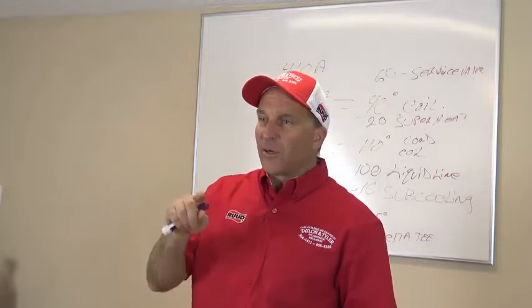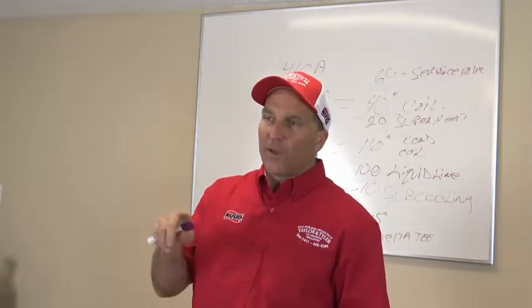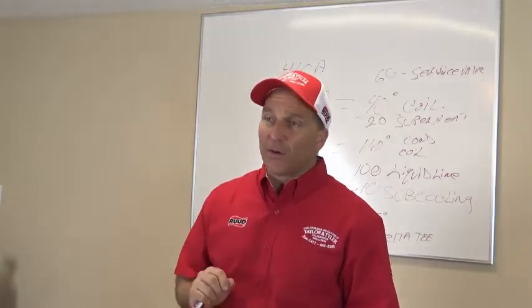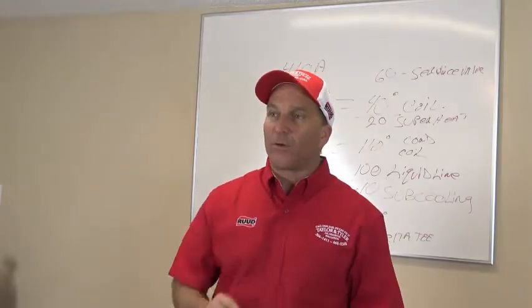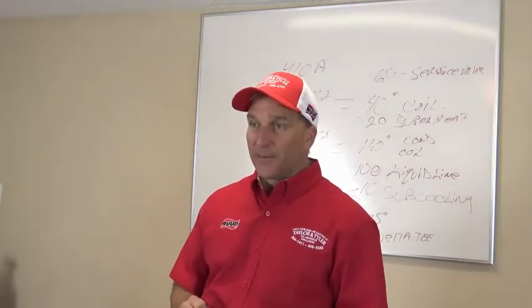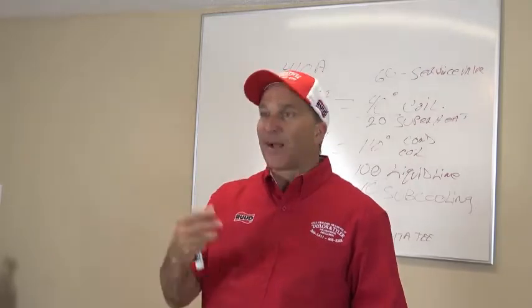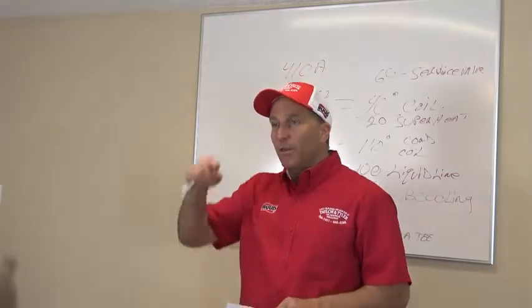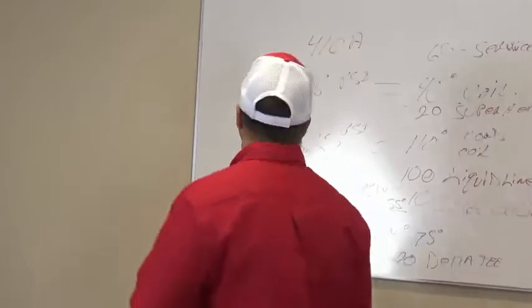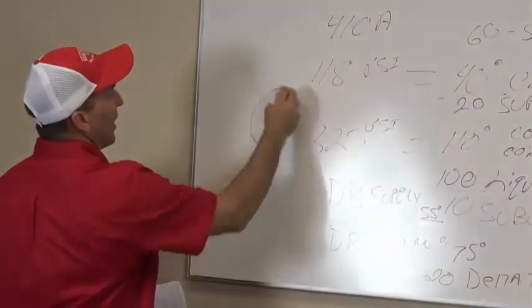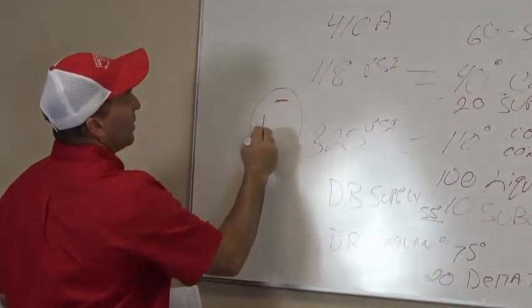The microfarads are MFD. So if you got a 440, 50 plus 5, you have 50 microfarads and 5 microfarads with 440 volts. You understand that? No? You know what a capacitor is, correct? Okay. Well, you got 3 terminals on the capacitor. Okay? Your 3 terminals on that capacitor. This one here, and this one here.